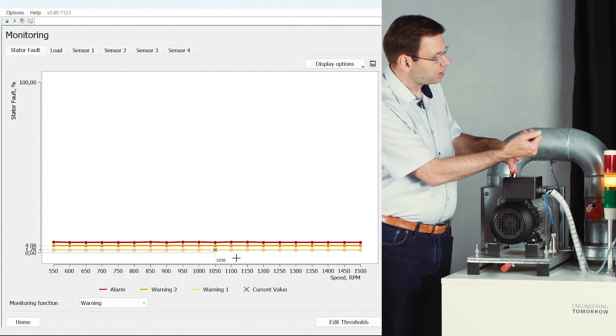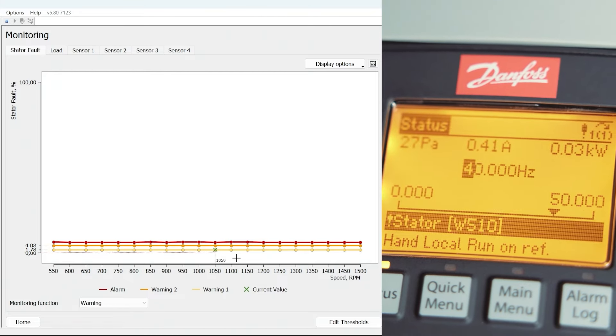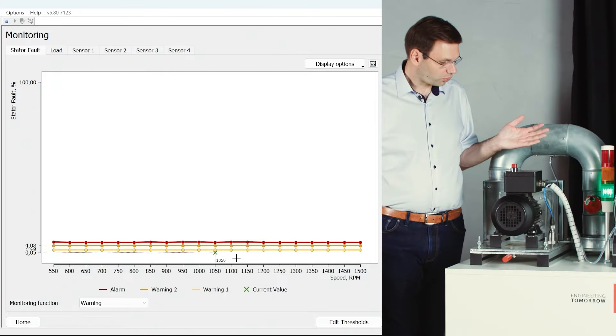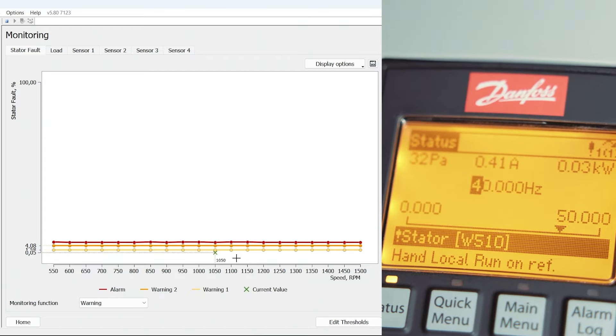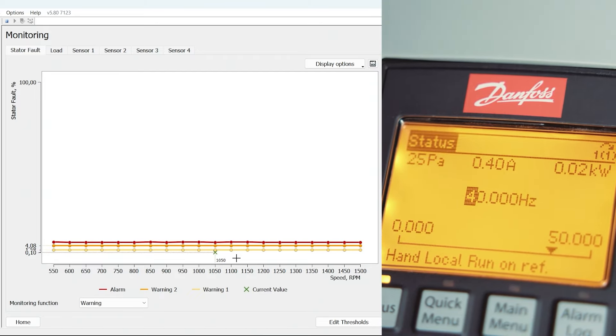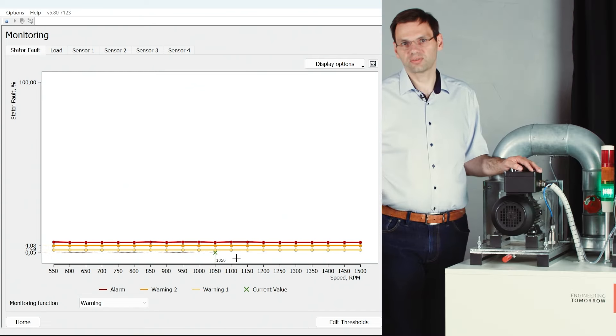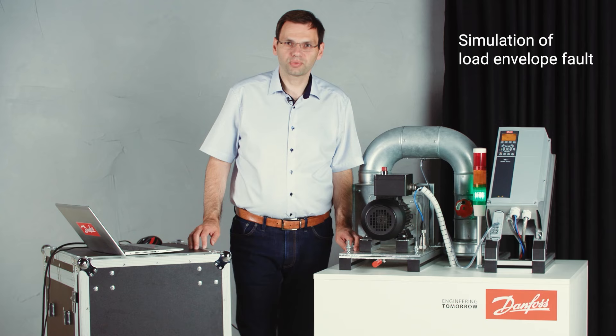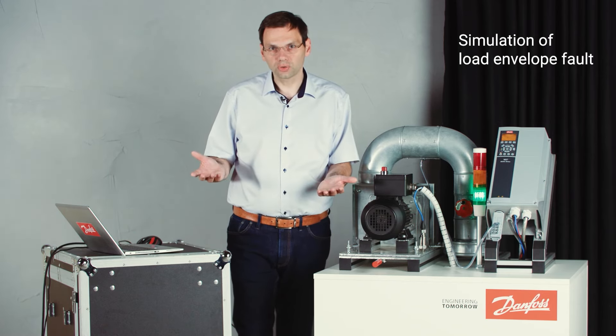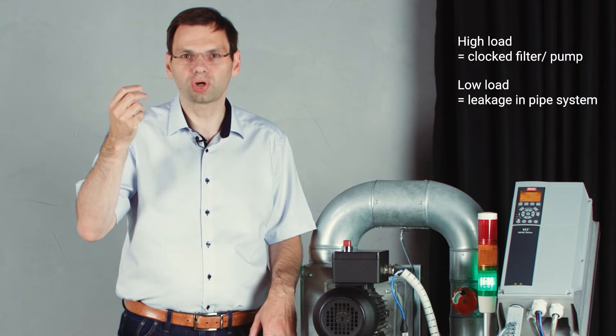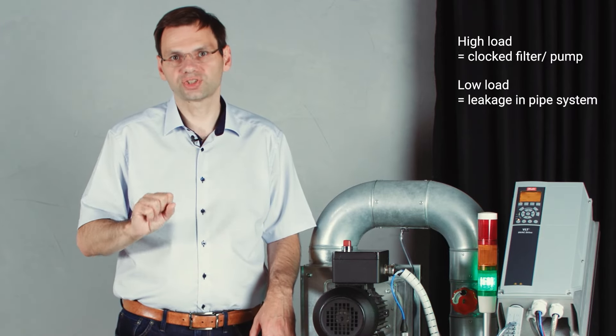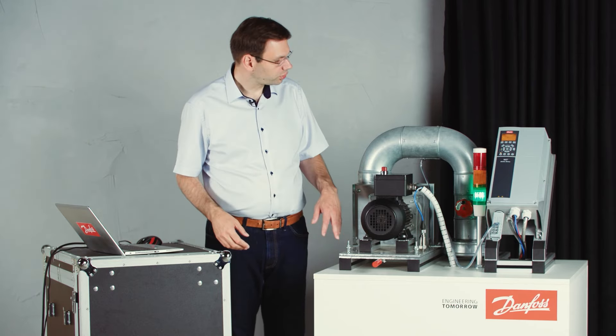On the display of the drive I also got a warning telling me there is a winding fault. When I remove the fault, everything turns back to normal and the green light is active again, showing that everything is okay. The next fault to demonstrate is the load fault, also called a load envelope. It is called an envelope because it has both upper and lower thresholds — we can detect a variation both upwards, when the motor runs heavier and needs to provide more torque, or downwards when the load is decreased.